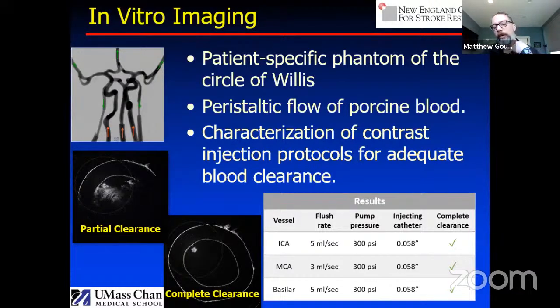So if we're injecting from the internal carotid artery, of course, with the ACOM and the PCOM, if we're imaging the MCA, there's other avenues for blood flow. And if you even have 3 to 5% of the field of view with erythrocytes, they basically attenuate the light, so you won't acquire a clear image. And so this is an example in a silicone phantom of blood that's circulating, porcine blood that's circulating, where this is not an adequate image because we're missing half the vessel. We have blood products here that's not allowing us to image very clearly. And this is an example where we have complete clearance and an adequate image.